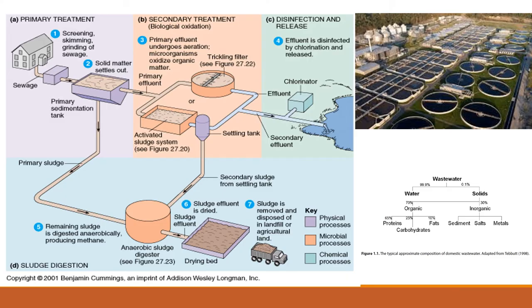Looking at a typical wastewater treatment plant structure, wastewater is 99.9% water and only 0.1% solids — including organic and inorganic solids. Inorganic solids are heavy and are removed by initial primary treatment steps through gravity settling. Organic matter is removed using biological treatment steps — trickling filters and activated sludge processes — where organisms feed on the organic matter, cleaning the water in the process.